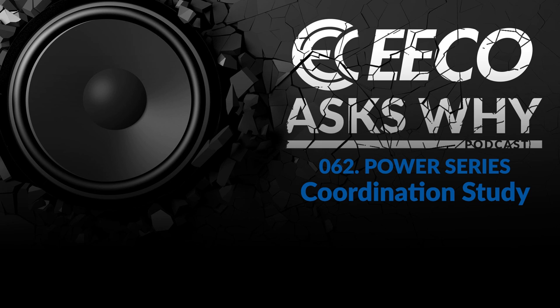We love to get to the why on EECO Asks Why. If somebody were to pop you in the elevator and say, 'Why do I need to do this?', what would be the answer? The reason to do a coordination study would be to make sure that not only is your equipment protected properly, but also that the user would be protected properly during the event of a fault. And the last thing is that you don't have unintended tripping of devices further upstream for faults that are much lower down the line — you want a localized fault to be tripped by the local breaker and not by a breaker five levels upstream.